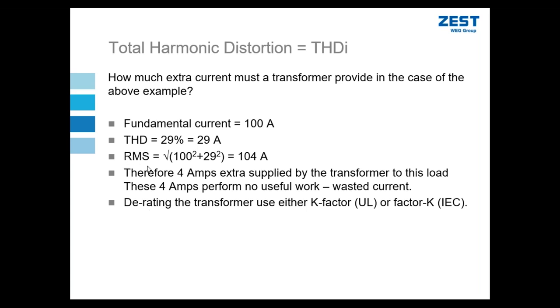But to find my true current, I need to do a root mean square. And if I do 100 squared plus 29 squared, and take the square root, I get a total of 104 amps. That needs to be supplied in this situation. Therefore, 4 amps extra is supplied by the transformer to this load, which performs no useful work. It is wasted current. So if that transformer is not dimensioned for that additional current, in this case, it's only 4 amps, but still, if it is not dimensioned to supply that additional 4 amps, the transformer could overheat or trip. Give some nuisance trips.